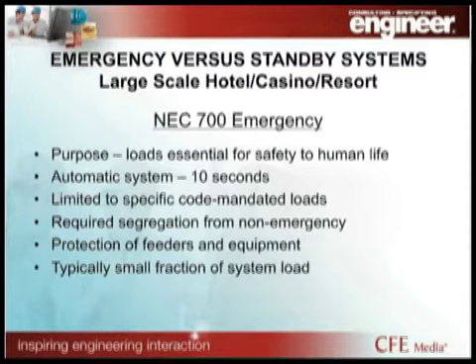From a segregation standpoint, when you're designing for emergency power, it's got to be segregated from all non-emergency. It's a little different in hospitals. Gerald was talking about where you can take life safety and critical branch and put it on one system where equipment is separate. For 700 and 701 loads, they're actually required to be segregated from each other. Protection of feeders and equipment, the code's very specific about how you have to protect feeders and the equipment that makes up the emergency system.